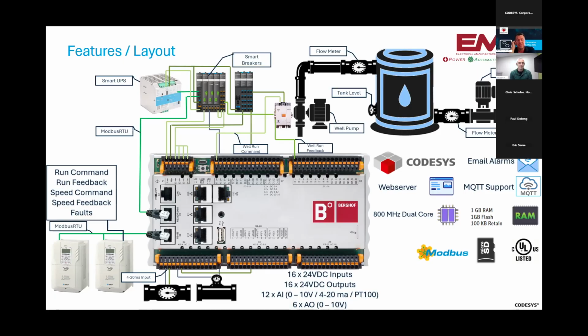So internally to the panel, our Modbus is on one channel for our UPS, our smart breakers. And then we're also looking at vibration and temperature monitors on those, if the customer so desires, flow meters, whatever you might want. And then on the VFDs, because they're mission critical, we allow them to be on their own Modbus channel. And then that way we don't have to worry about something else going wrong on the Modbus to prevent us from controlling the booster pumps. Because in the end, maintaining pressure and maintaining tank level here is what the customer needs. So with any kind of catastrophic failure, we want to make sure we're still maintaining pressure in that system and keeping the tank full.